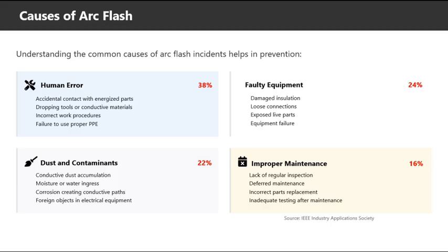Dust and contaminants account for 22% of incidents. Conductive dust accumulation, moisture or water ingress, corrosion creating conductive paths, and foreign objects in electrical equipment can all create conditions that lead to arc flash. This is why housekeeping and environmental controls are so important in electrical work areas.